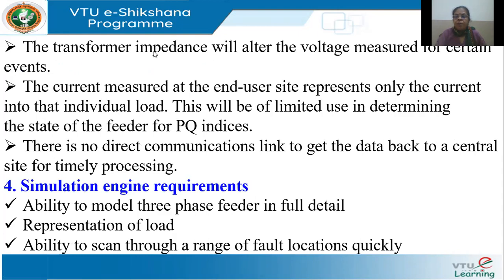And the transformer impedance will alter the voltage measured for some events, because impedance affects the fault currents. And so the estimate may be different from the actual value. If I put a monitor at the customer premise, or if I estimate the value at the customer premise, it will give me only that particular load, right? For the entire feeder, it may be difficult to get the PQ indices. So I have to judiciously place the monitors. And setting up communication links to get data directly, that is smart communication, is very expensive and will cost a lot of money. Okay, these are some of the issues.